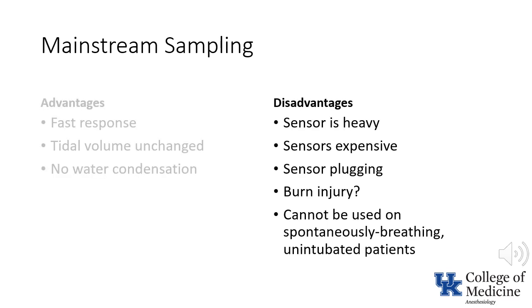The sensor is heavy and its use can result in inadvertent extubation. In addition, the sensors are expensive. They are intended for reuse and not disposable, so inadvertently discarding the sensor results in increased replacement expense. Furthermore, because the sensors are reused, they must be sterilized between uses, again adding to the expense.